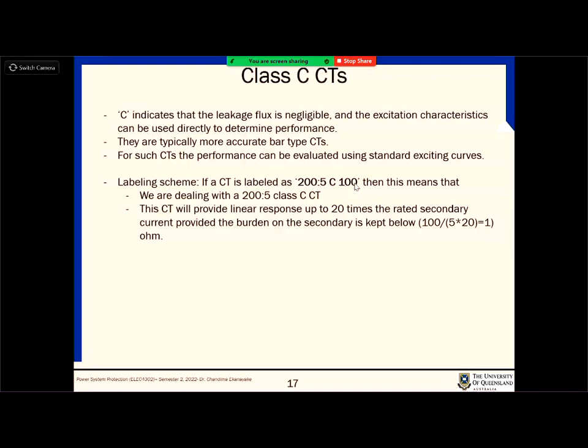You got the point? The CT will provide linear response up to 20 times the rated secondary current, which is 20 times 5, right? This 100, and then the burden on the secondary is kept below 1 ohm. What does this 100 mean? Do you remember that previously I said the 100 volt rating is defined in such a way that if you send 20 times the rated current, then you need to find the standard burden which limits your secondary voltage at that level. So that is what 100 means.